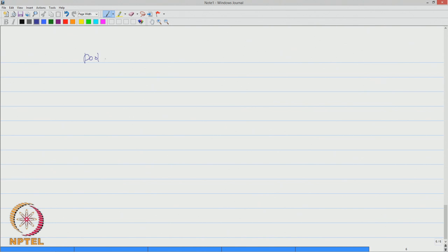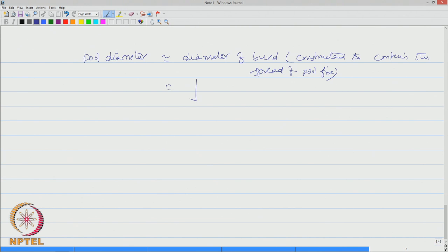The pool diameter will be approximately equal to the diameter of the bund, which is generally constructed to contain the spread of fire. So this is nothing but root of 4A by pi, where A is the area of the bund in square meters.